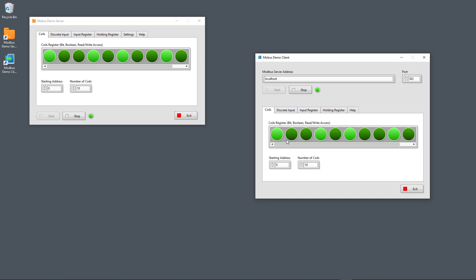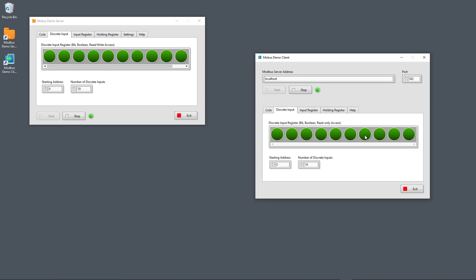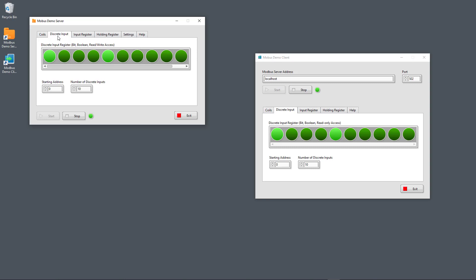That's the coils — for coils you can write values from the client to the server and also read them from the server. While for discrete input, you cannot set values from the client because it's read-only, so you can only set these values from the server, but they are updated here on the client. So that's discrete values: coils for both reading and writing, or discrete input for only reading values.